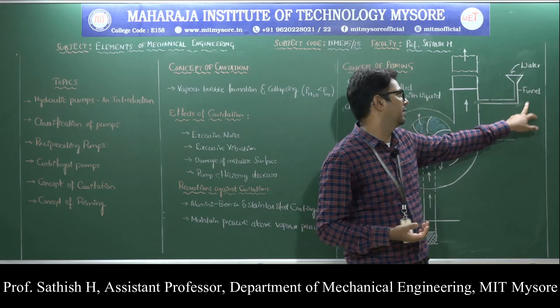I have retained the sketch of a centrifugal pump here, and I have made this attachment here. This is a funnel where the water is poured. Make sure that before starting a pump, you pour the water so that the whole casing, the impeller portion and the suction line are filled with water. That removes the air trapped in the pump. Then you start the pump, and the pump will work properly.